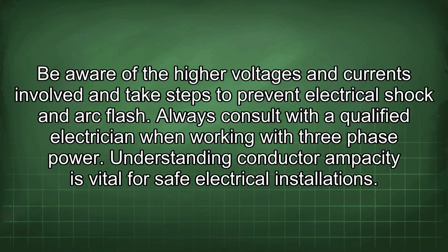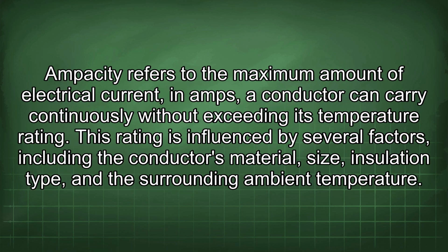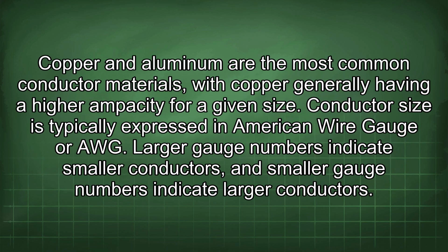Understanding conductor ampacity is vital for safe electrical installations. Ampacity refers to the maximum amount of electrical current, in amps, a conductor can carry continuously without exceeding its temperature rating. This rating is influenced by several factors, including the conductor's material, size, insulation type, and the surrounding ambient temperature. Copper and aluminum are the most common conductor materials, with copper generally having a higher ampacity for a given size.